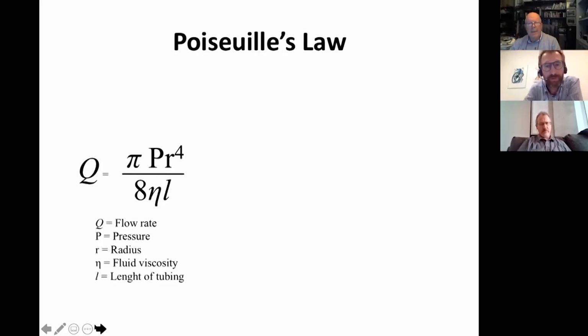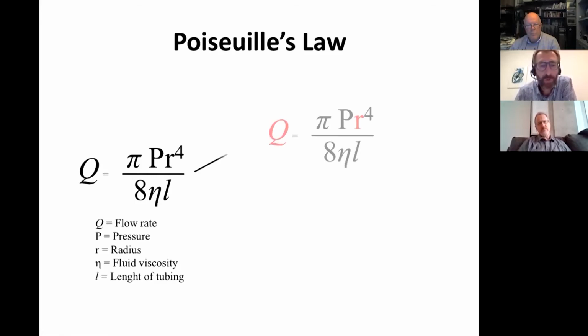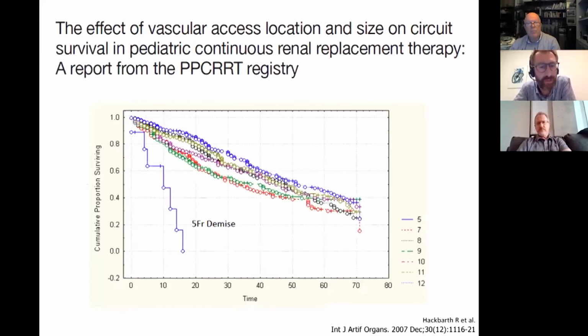And we know from the Poiseuille law that the flow inside of a catheter or inside of a tubing system depends on the pressure and depends on the fourth power of the radius, and it's inversely associated with the length of our tubing. So if our aim is to increase the flow inside of a catheter or inside of an extracorporeal line, what we should do is to increase the radius. And this is exactly what has been demonstrated by the prospective pediatric CRRT registry. This is a quite famous study.